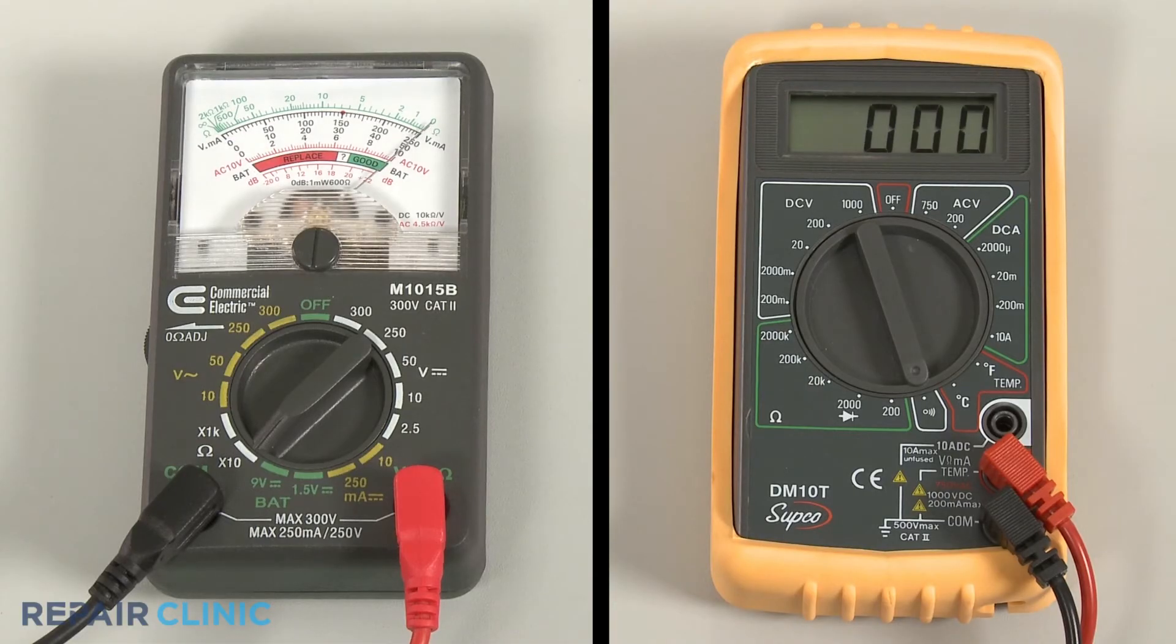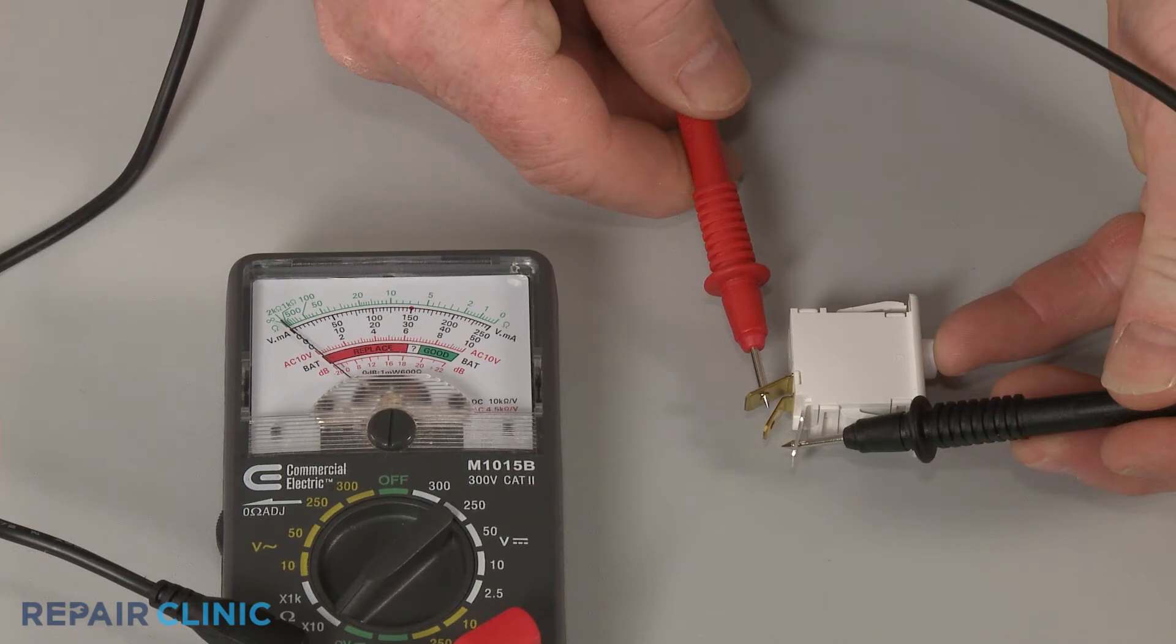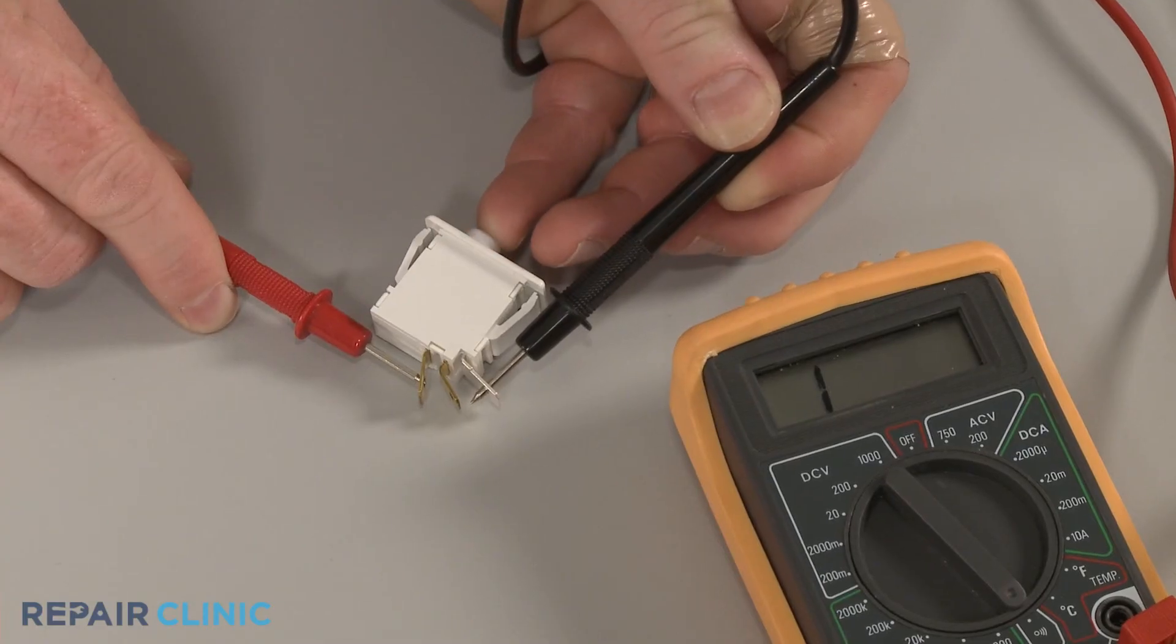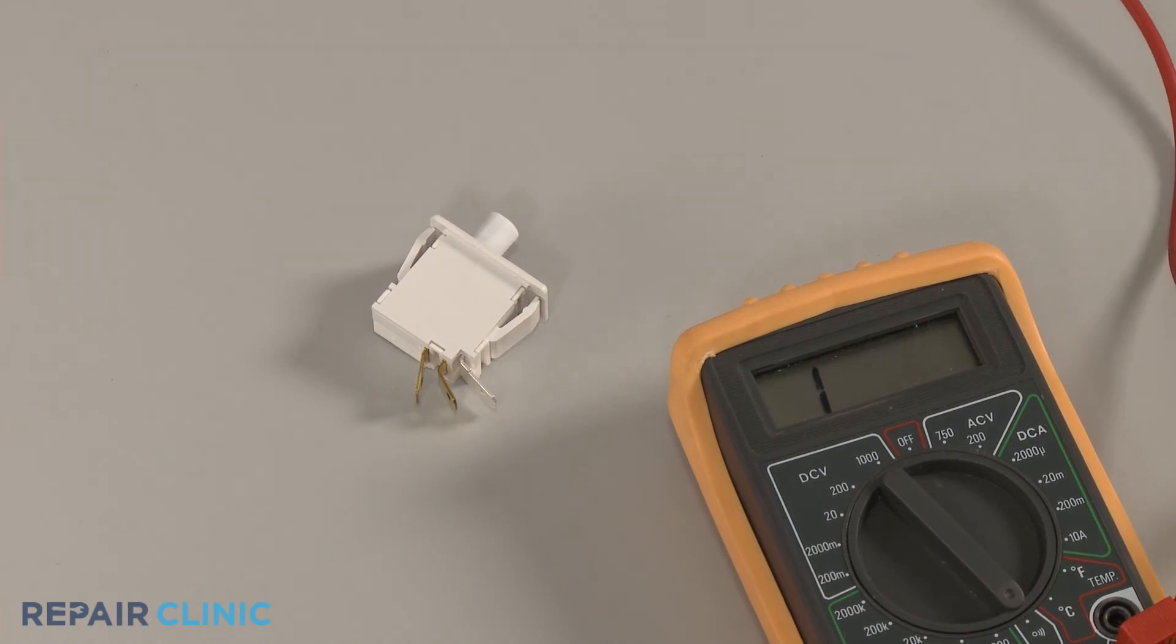If the meter reading shows zero ohms of resistance, the switch has continuity. If the needle does not move, or the digital display does not change significantly, there is no continuity, which means the switch is defective.